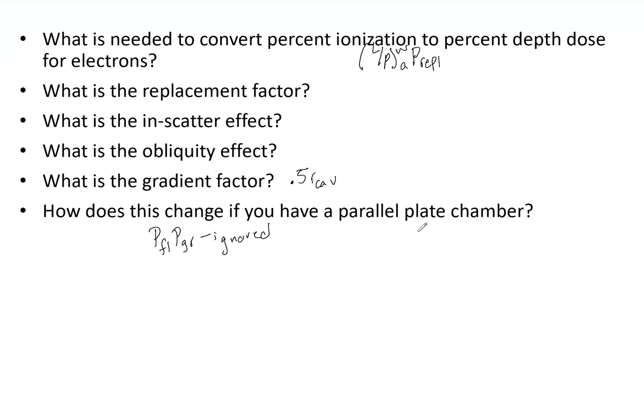However, that L over rho correction does need to be applied. And again, the gradient factor and fluence can be ignored because your effective point of measurement is now the front surface of the parallel plate chamber, not within this ion chamber.